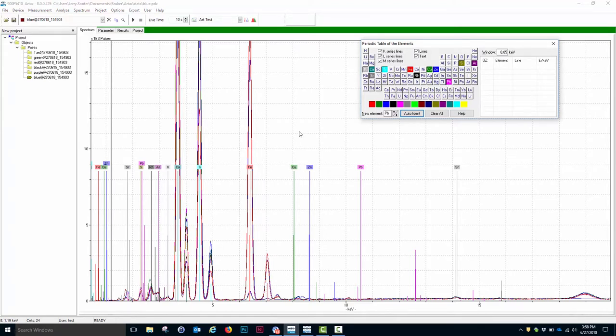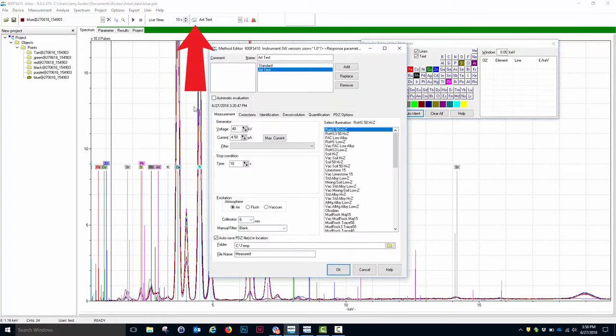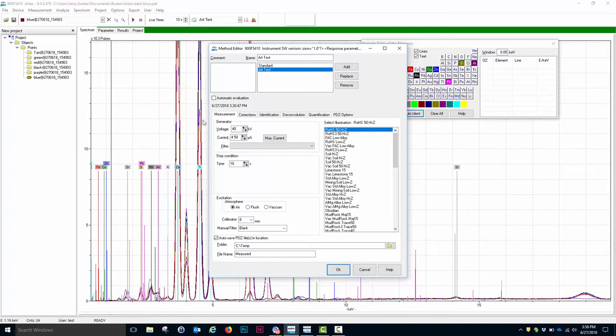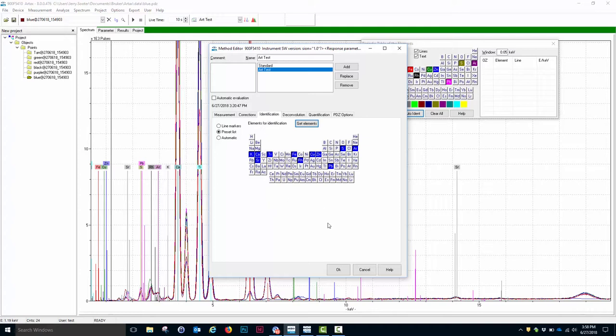Finally, what I want to do before I leave this is I want to save those lines, and the way I do that, as I go back to the Method tab, I go to Identification, I click Preset Lines, and Get Elements. This imports all of the lines that I've just chosen on the spectra.